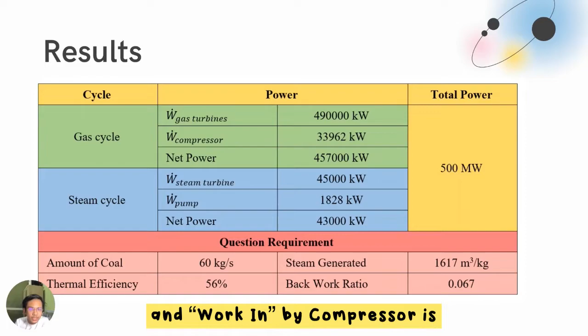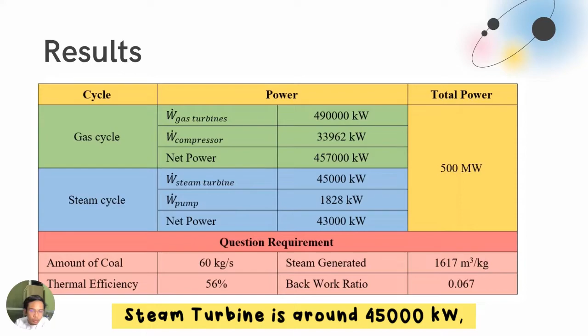The work out from the gas turbine is 490,000 kilowatts, and work in by the compressor is 33,000 kilowatts. The work out from the steam turbine is around 45,000 kilowatts, and work in by the pump is around 1,800 kilowatts. Combining the net power from the gas cycle and steam cycle gives a total power of approximately 500 megawatts.